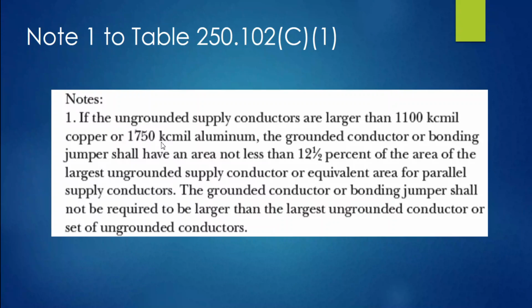Okay, so you could be doing this based on the number of parallel sets, and you could do the 12.5%, and it could result in a bonding jumper or grounded conductor that may be larger than the largest ungrounded conductor or set of ungrounded conductors. And of course, they're saying you don't have to do that. Okay, very rare, I think, to come into that. For most people who are going to run into it, you're going to have examples like I did, where you have parallel sets of 500s, and when you do the 12.5%, it's not going to be larger than what you had as far as the conductors.